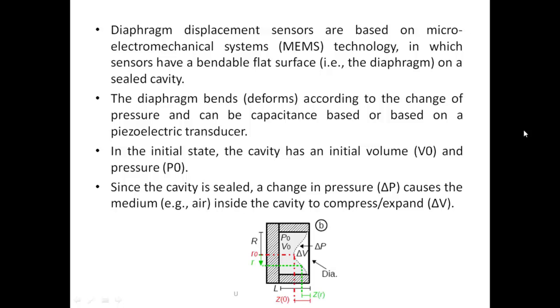Diaphragm displacement sensors are based on micro electromechanical systems technology, in which the sensor has a bendable flat surface on a sealed cavity. The diaphragm bends according to the change in pressure, and can be capacitance-based or based on a piezoelectric transducer.